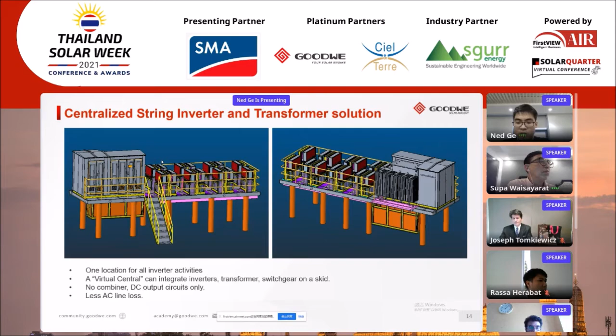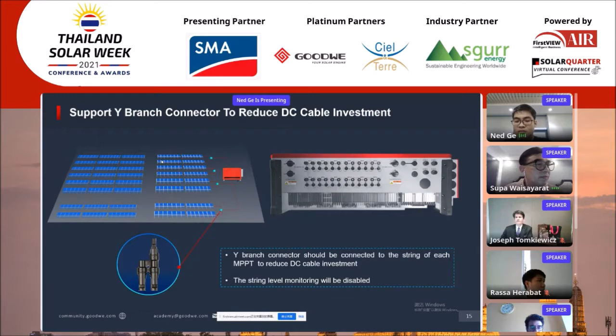Based on the central virtual design, this Y branch connector will further lower system investment. The parallel connection is accomplished by joining the positive of two strings together as well as the negative of two strings together. The combined current is then transported by a 6 millimeter square DC cable to our inverter. In this scenario, the combined current can reach more than 25 ampere. Note that the two models can still support this large current if each MPPT only connects one string, but the string level monitoring will be disabled, while the MPPT level monitoring still exists.